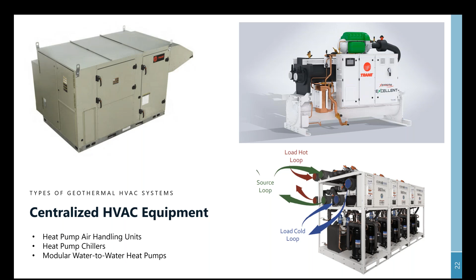Other centralized HVAC system equipment types include heat pump chillers. In the top right corner, you see an example of a heat pump chiller. These are typically found in fairly large applications where you have a pretty substantial building heating and cooling load. These heat pump chillers are capable of producing both chilled water and hot water, and capable of energy recovery from the production of chilled water to put that energy directly back into the hot water stream. Another type of application is the modular water-to-water heat pump. These systems are sometimes referred to as six-pipe chillers or six-pipe heat pumps, and effectively have a cold loop, a hot loop, and a source loop. The source loop is going to be your geothermal loop. These systems are also capable of producing chilled water, hot water, or simultaneously creating both chilled water and hot water.